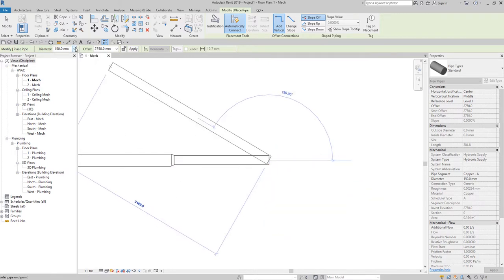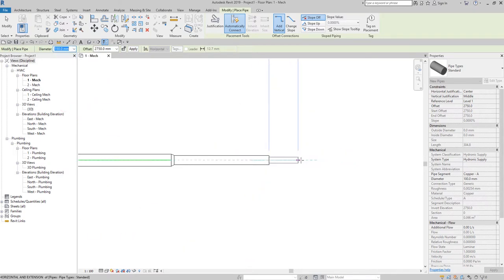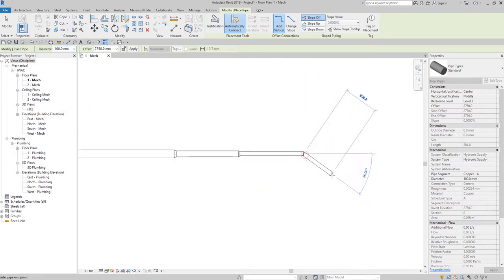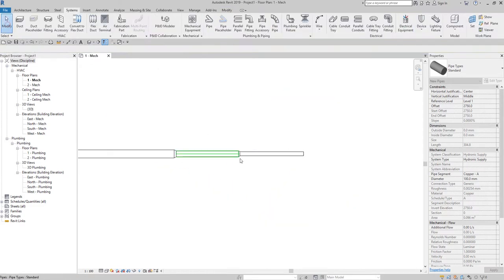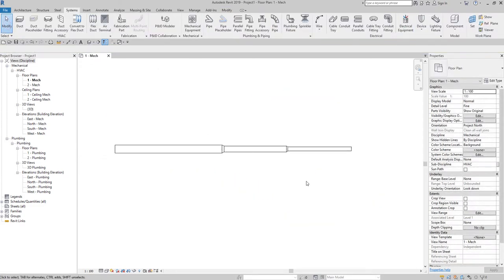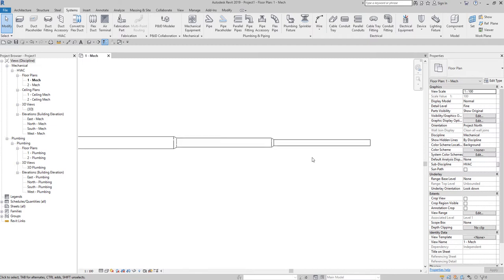I'm going to change the diameter to 150 — there you go. Then let's create another segment but this time with a 100mm diameter. Now, although piping is concentric, you can specify the justification for different pipe sizes. According to Autodesk Revit, the Justification Editor lets you align the top, bottom, or side of pipes in a section of the system.